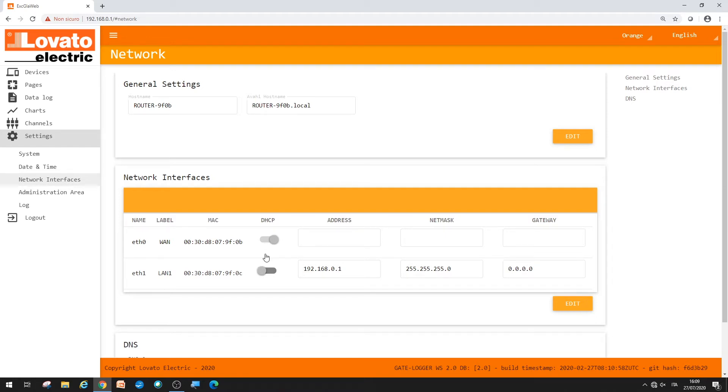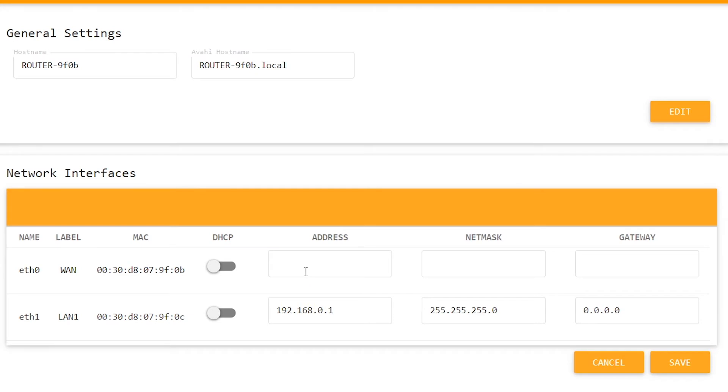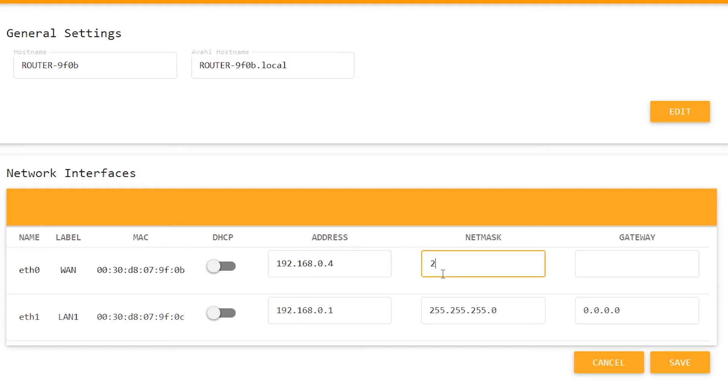Deactivate the DHCP option and assign the gateway data logger an address agreed with your network operator. In this case, 192.168.0.4. Subnet mask 255.255.255.0. Save and wait for the beep from the gateway.